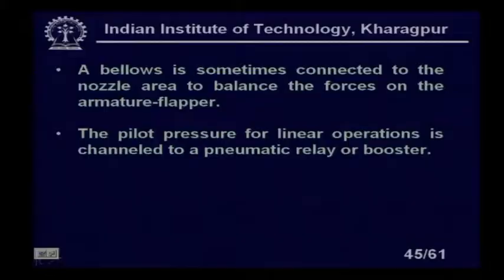Okay, that pilot pressure or the back pressure which is coming, that is going to the relay for boosting operations, right. That means the pressure might be small, and a small movement will be made. So, we have a more linear region. Once it goes through the relay, I will get a 3 to 15 psi pressure.